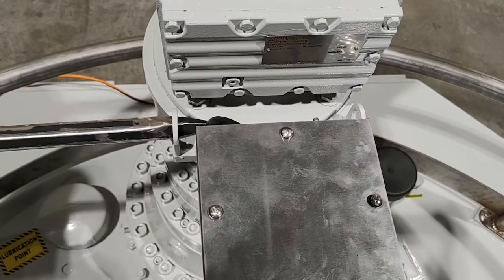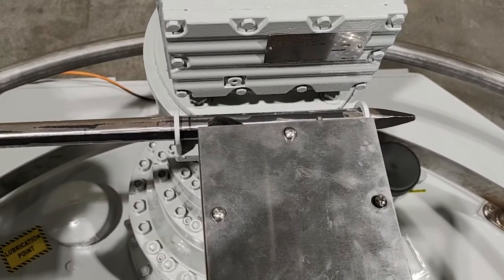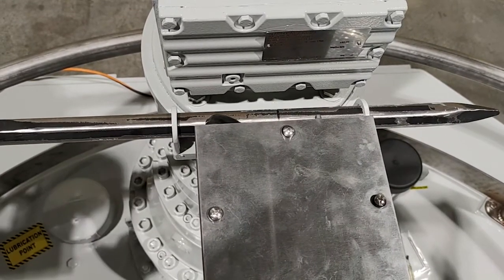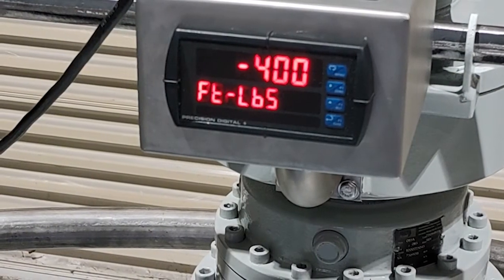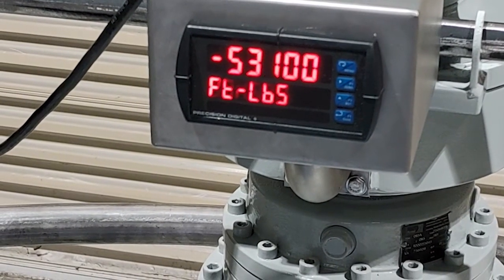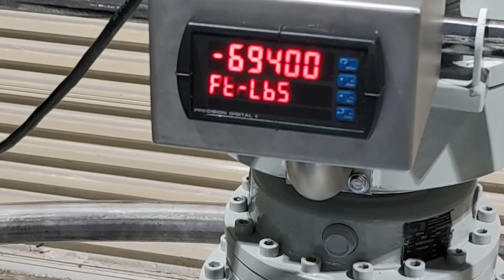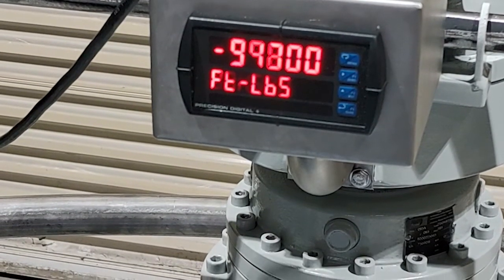One common mistake that can be made during calibration is inserting the pipe into the 2 lugs from the wrong direction. This can result in a negative display value during operation. Verify that your setup is correct for the direction of rotation of your drive unit and repeat the calibration procedure.